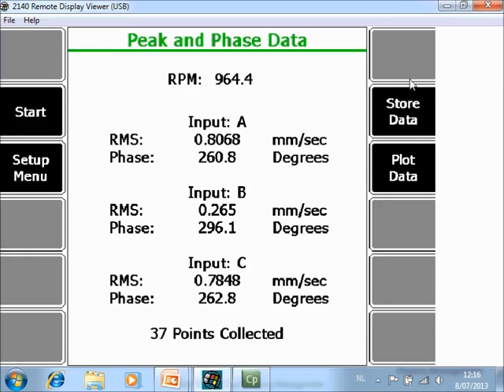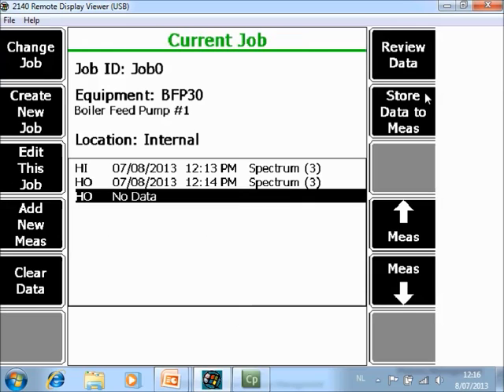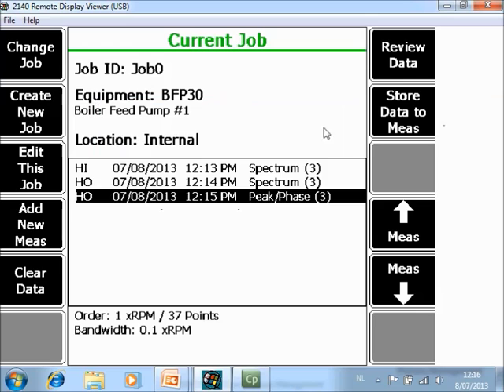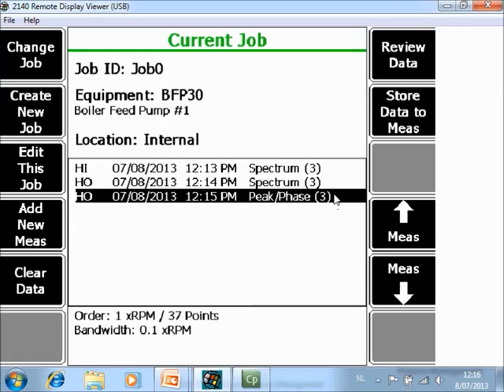And now also you can store the data by F8. I will store it to this point. So store data to measurement point. And as you see, the labeling is correct. And this data is now stored in the job mode on the analyzer. All this data can be also transferred to the software. And this setup is similar if you want to collect waveform true zoom, overalls, and so on.